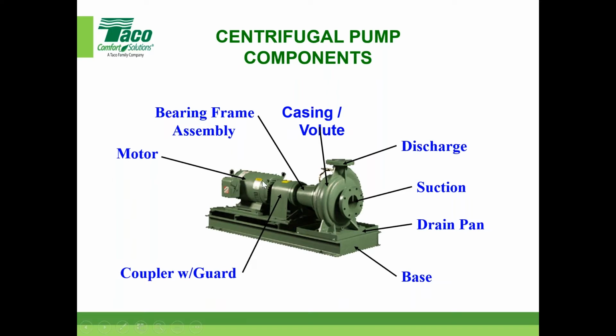And then there's the motor right here. It's a pretty standard premium efficiency motor. And then you have a coupler. There's couplers underneath here, and there's a coupler guard. Pump manufacturers' I&O manuals will explain in there that this base needs to be grouted. It needs to be properly aligned, and it needs to be grouted. And there's a whole section in the manuals on that.